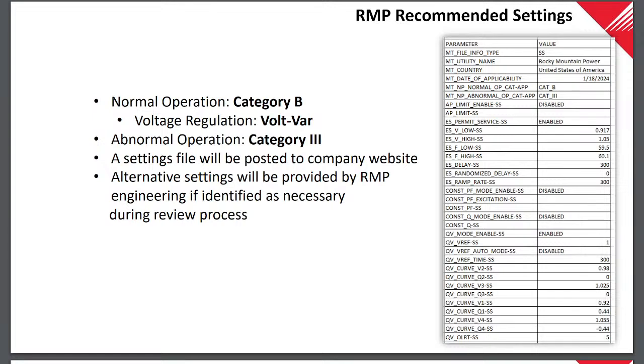I think it's need based, because the volt-watt function does take away some of the output from the inverter, so they're not going to be able to produce as much. We lean towards not taking away from the interconnection customer's generation capability, so we look at that first, and I'd see volt-watt as secondary. If volt-var doesn't work, then we'd go to volt-watt as the next step.